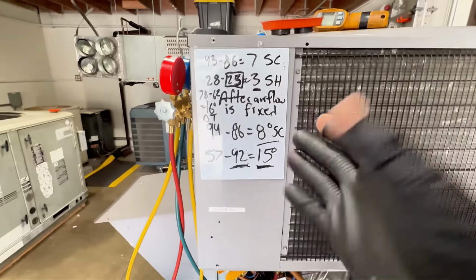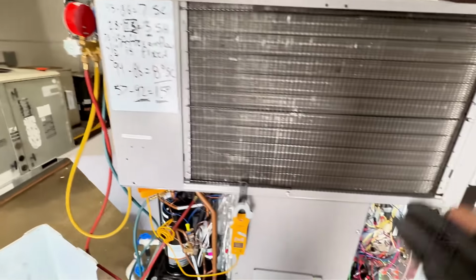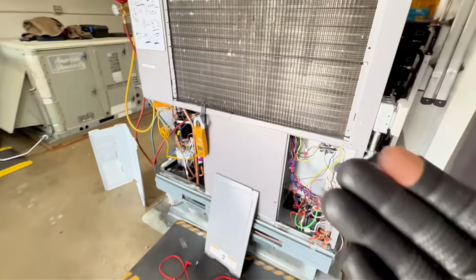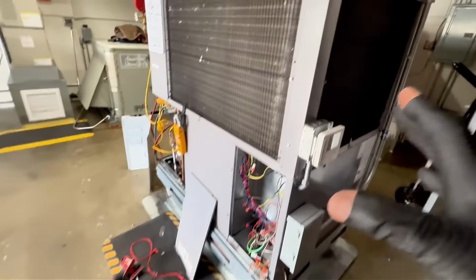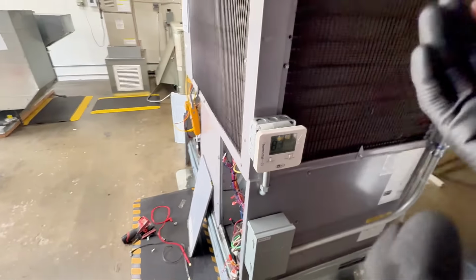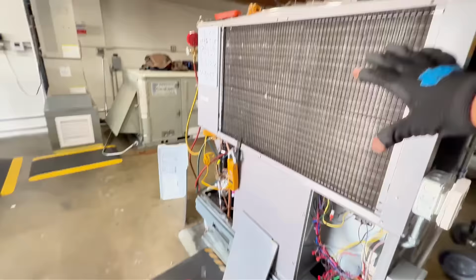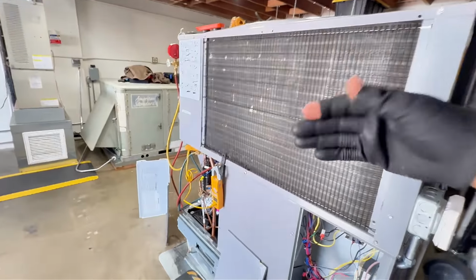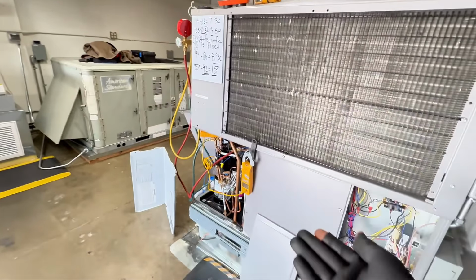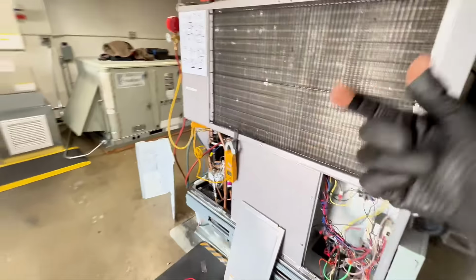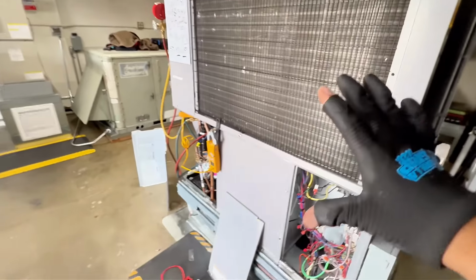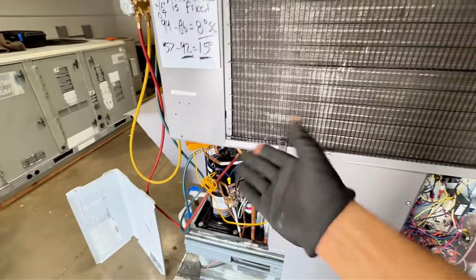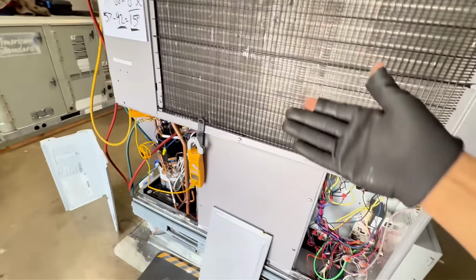So with the service call, just doing a recap. Always start off with what's easy first. Know your unit. Check airflow. You should not have a dirty condenser. Filter should be swapped. Evaporator coil should be clean. Your blower motor should be spinning pretty well. Before you gauge up, check airflow, and have it run for 10-15 minutes.